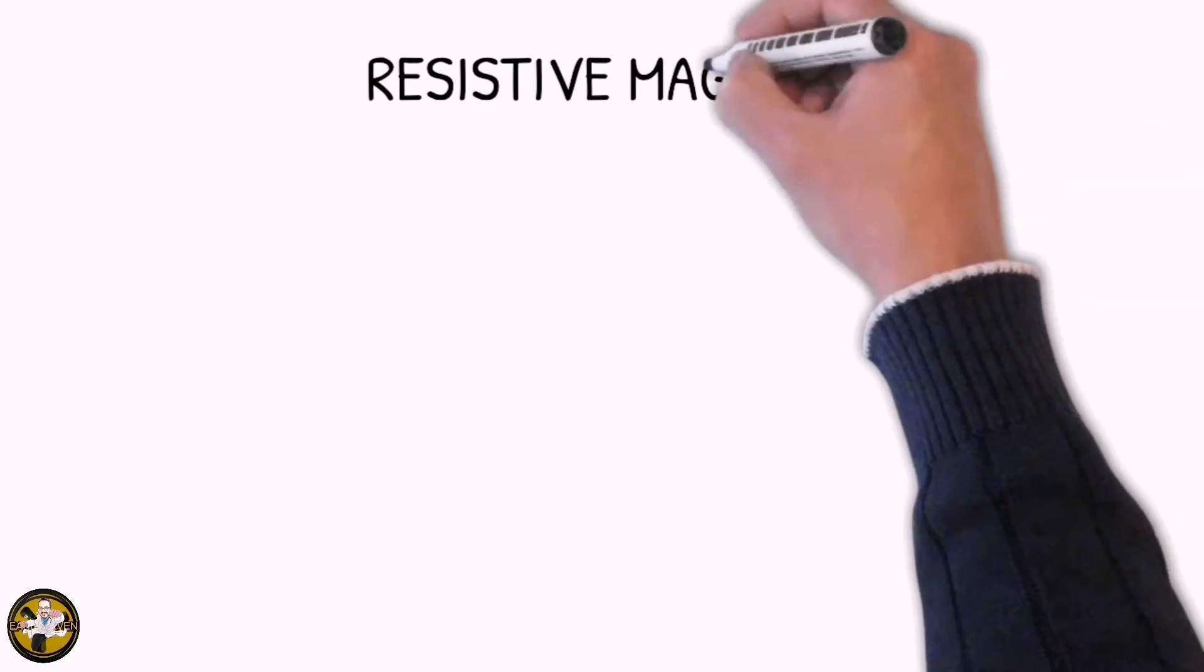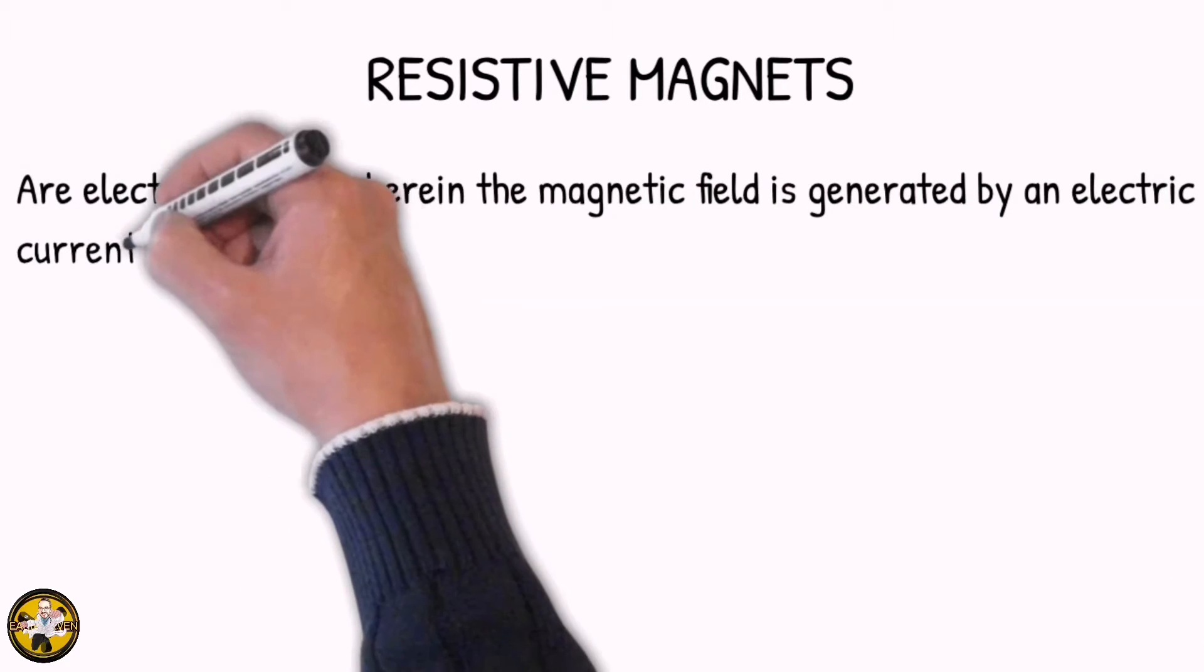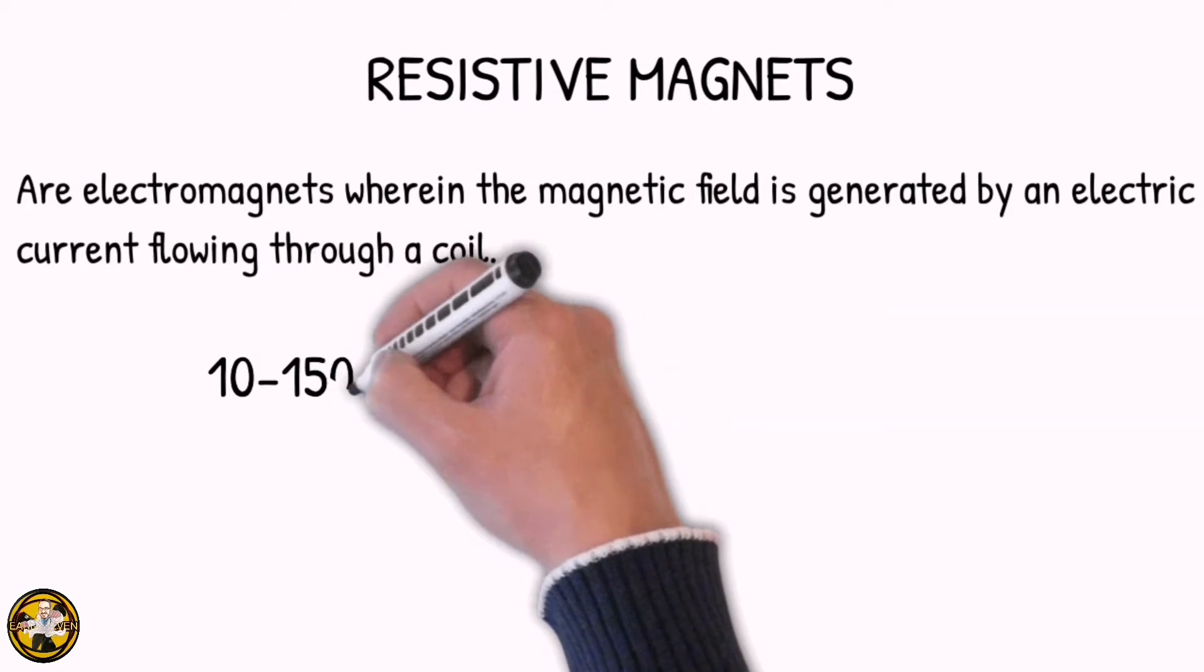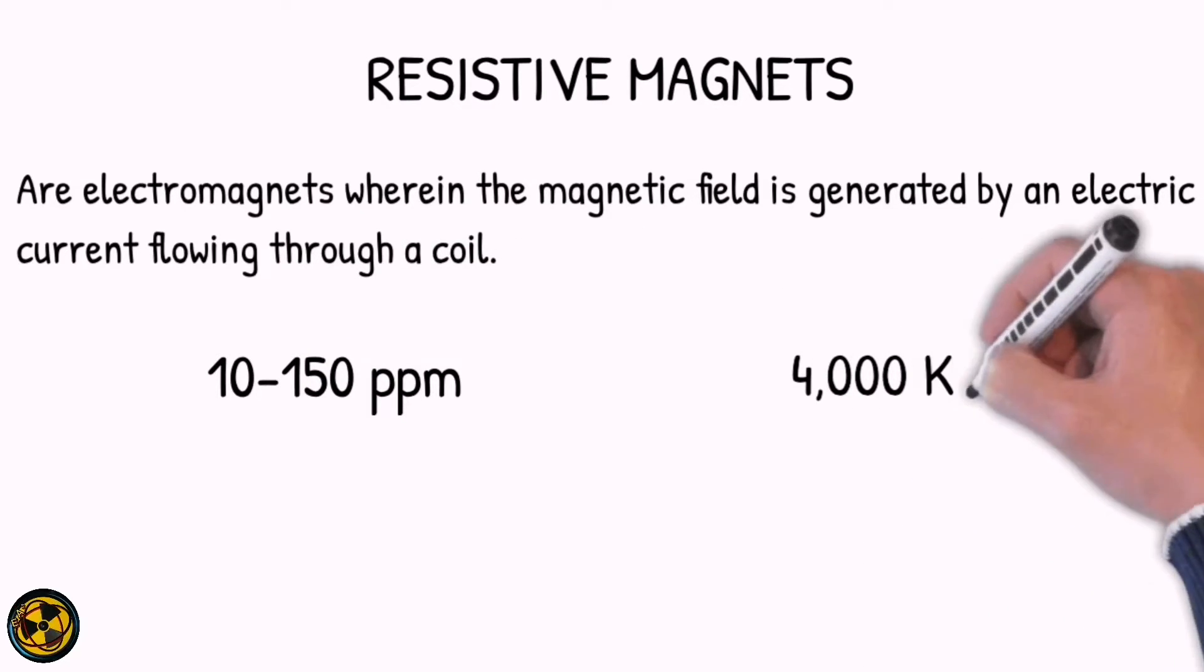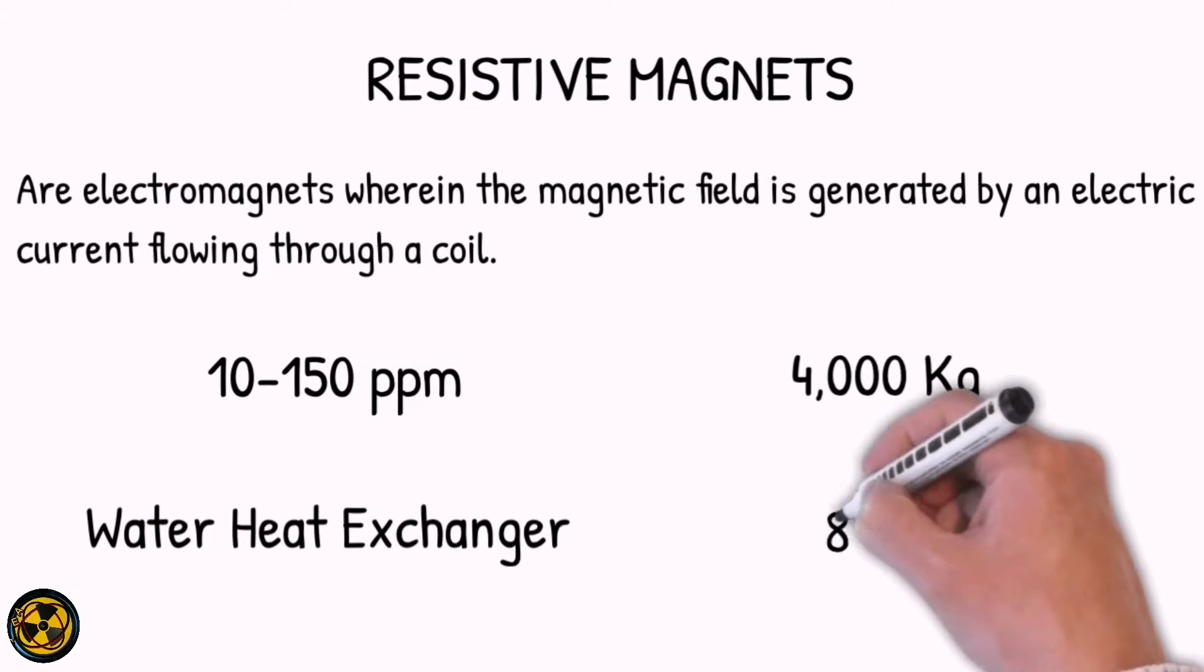The second type of magnet is the resistive magnet. These are electromagnets wherein the magnetic field is generated by an electric current flowing through a coil. Magnetic field homogeneity is 10 to 150 ppm, weight is approximately 4,000 kilograms, cooling system used is water heat exchanger, and the power consumption is 80 kilowatts.